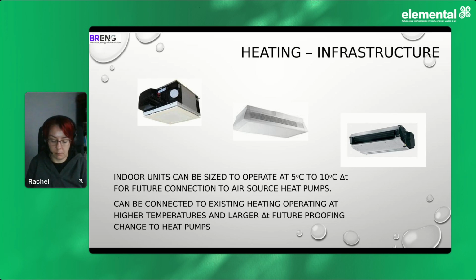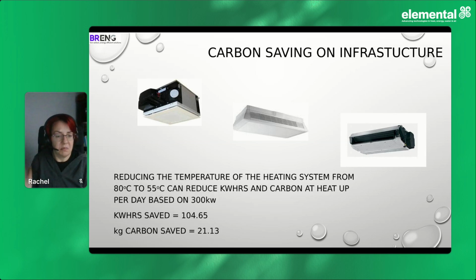The other benefit of using this on a standard heating system is you can actually reduce the water temperature that your boilers are actually generating. And by reducing the water temperature, you prolong the life of the boiler, but you reduce your carbon footprint every morning you switch your boilers on. Because what you're doing is you're heating the water up to 55 degrees rather than up to 80 degrees. And that 25 degrees of energy you've not used does save quite a lot of energy.